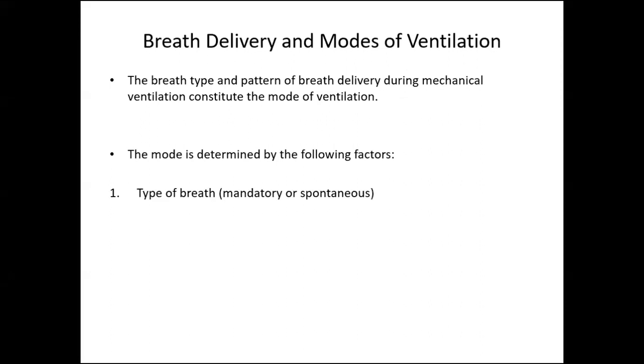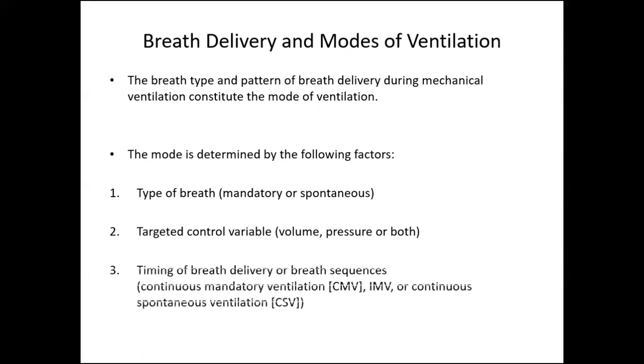So for type of breath, you have two breaths. One is mandatory breath and one is spontaneous breath. And you have a control variable, whether you're controlling volume or pressure or both, and timing of breath delivery. So whether you are going for mandatory ventilation, or intermittent mandatory ventilation, or spontaneous ventilation. These are three things which will determine your mode.